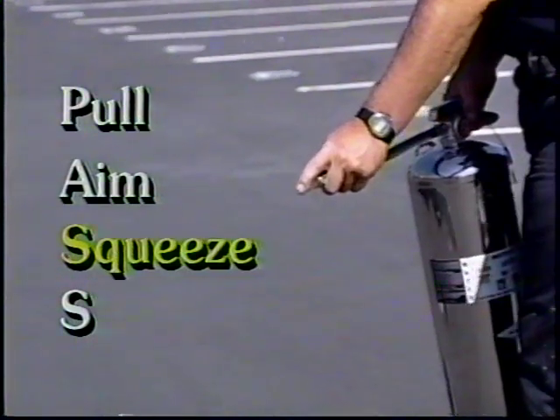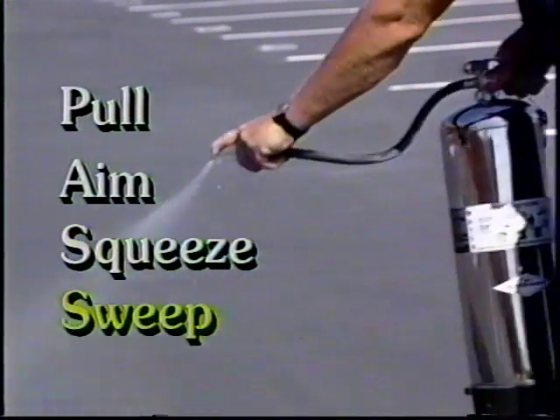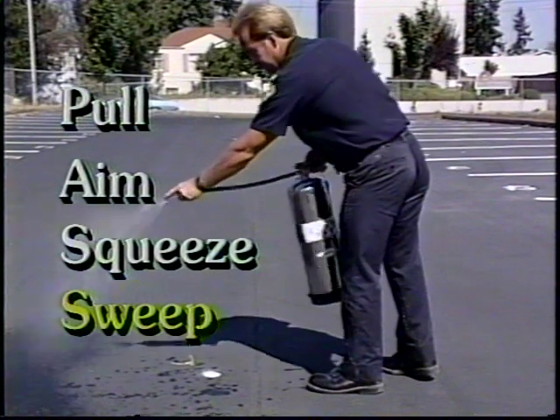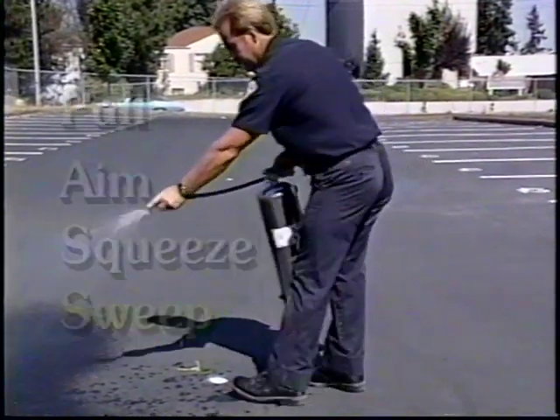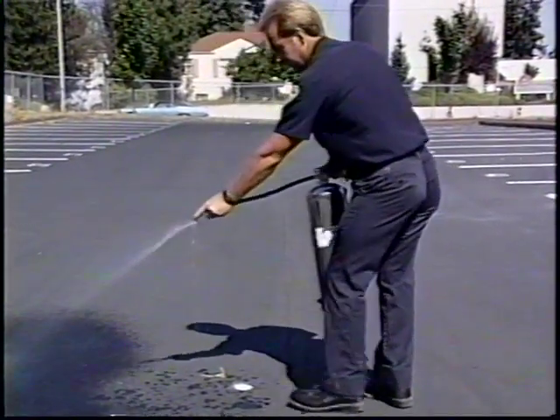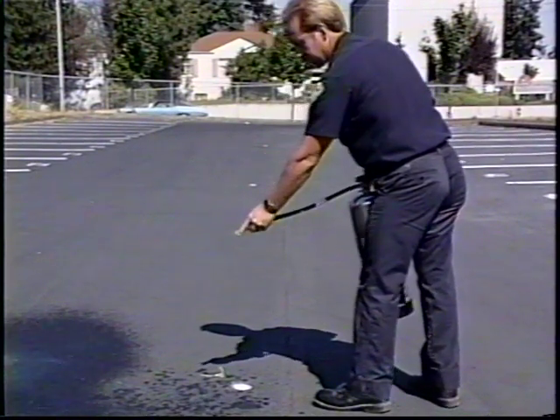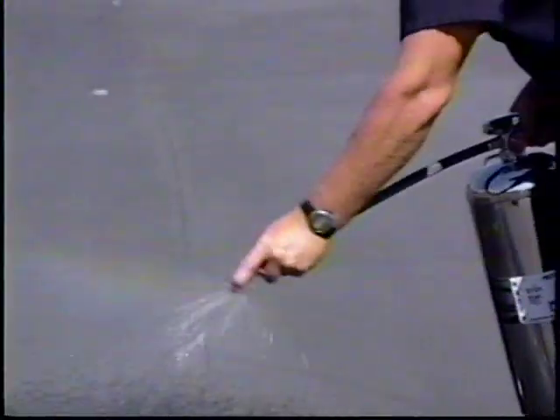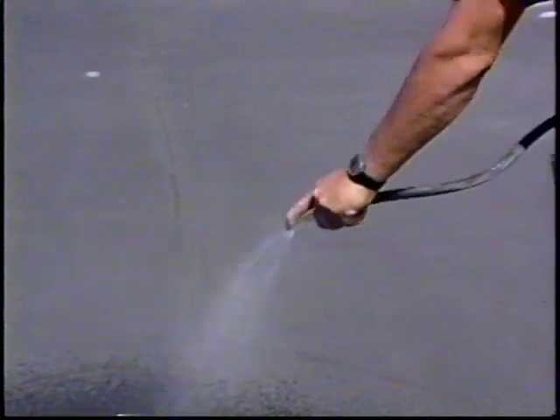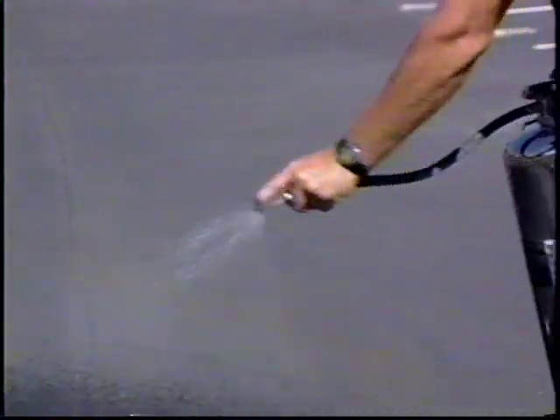The second S stands for sweep the nozzle back and forth at the base of the flames to disperse the agent. When the fire seems to be out, wait and watch for smoldering hot spots. Apply additional agent as needed. Don't leave until you are sure that the fire is out.